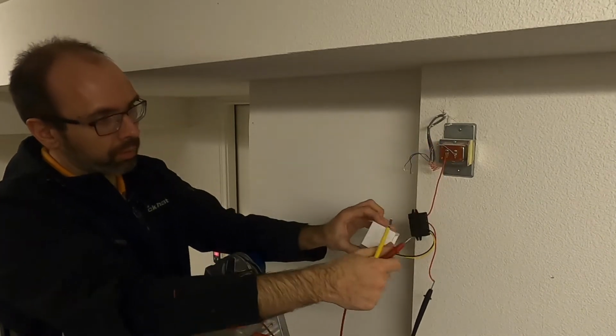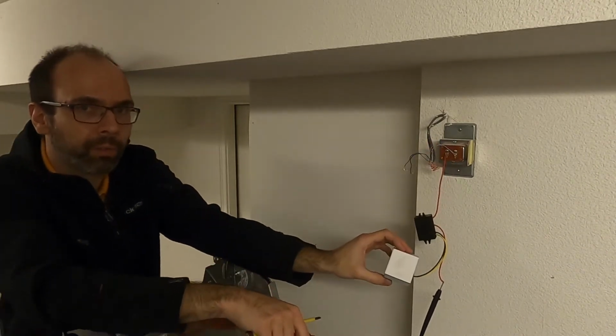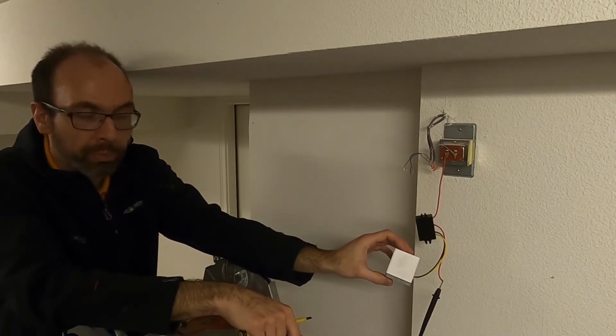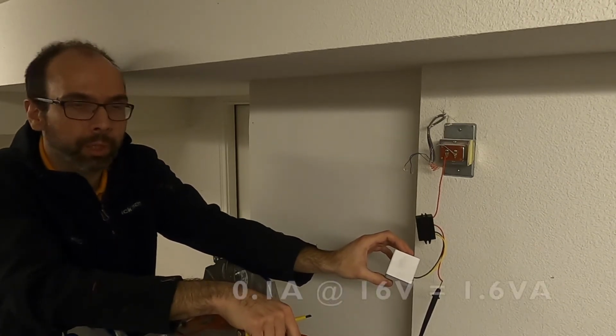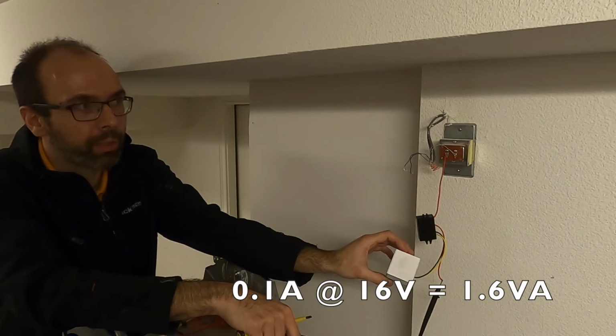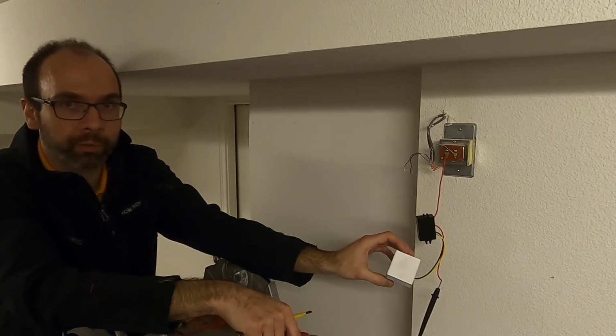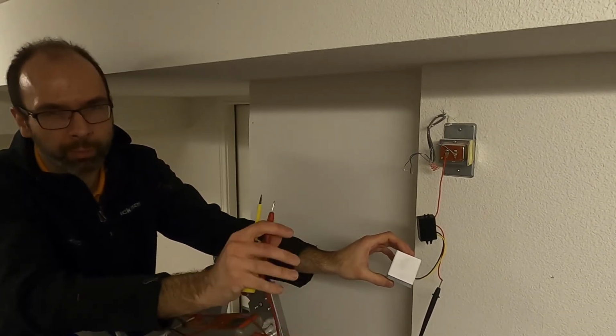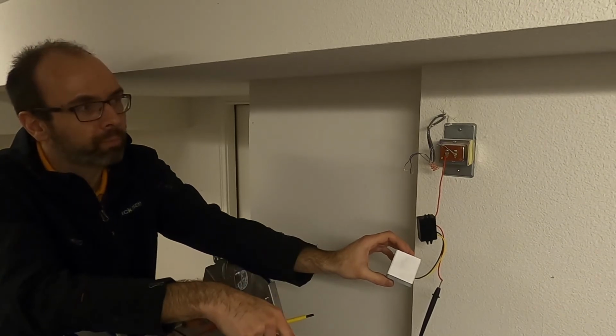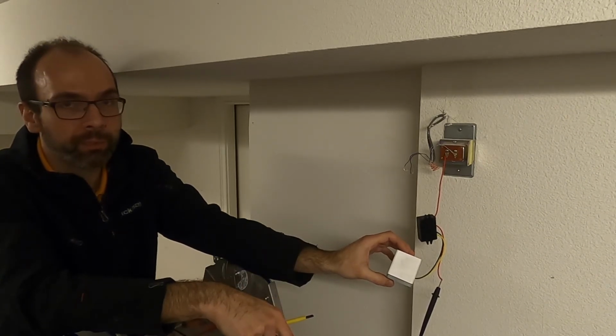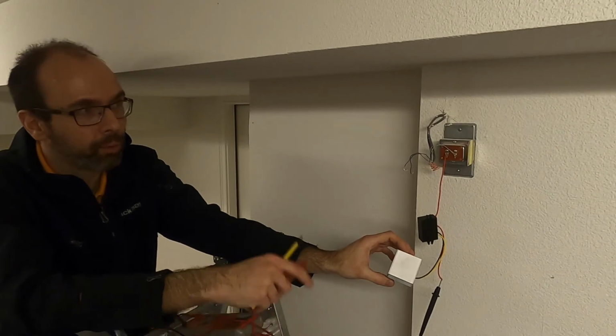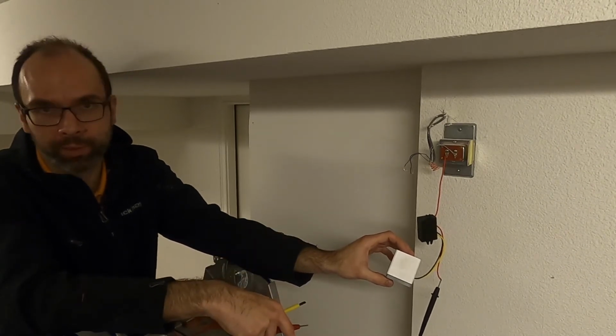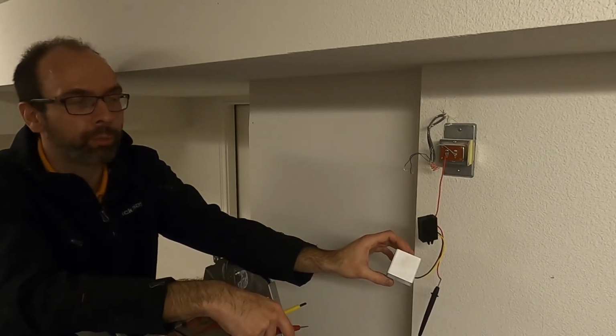So it doesn't use a lot of power, only approximately 100 milliamps at 16 volts. That's approximately 1.6 volt-amps, or 1.6 watts, approximately. That's good news because it tells me that, in practice, I do have enough capacity on that transformer. In theory, I don't. In practice, I do.